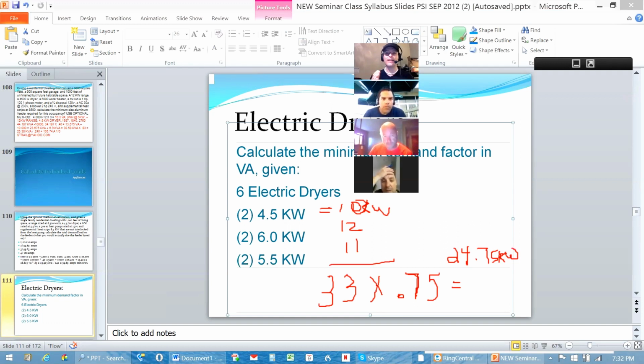But if we're looking at the neutral for a residential dwelling, there's an allowance under 220.61 on page 71. If you look at it real quick, it gives you an allowance to take a value of 70% against a range or a dryer in a residential dwelling against the calculated values under the tables as well. So in this case, under B1 on page 71, at the very bottom right-hand corner, 220.61(B)(1).